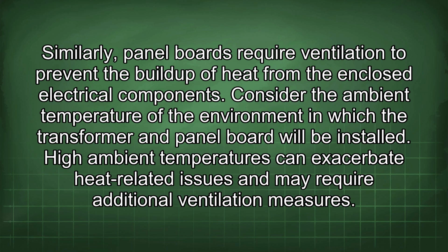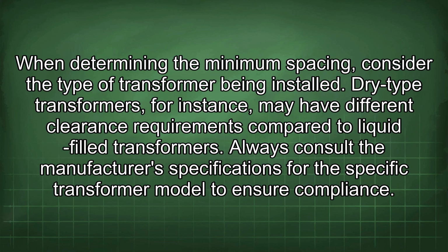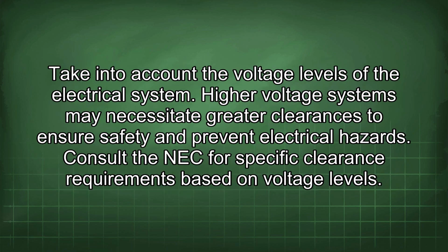Similarly, panel boards require ventilation to prevent the buildup of heat from the enclosed electrical components. Consider the ambient temperature of the environment in which the transformer and panel board will be installed. High ambient temperatures can exacerbate heat-related issues and may require additional ventilation measures. When determining the minimum spacing, consider the type of transformer being installed. Dry-type transformers, for instance, may have different clearance requirements compared to liquid-filled transformers. Always consult the manufacturer's specifications for the specific transformer model to ensure compliance. Take into account the voltage levels of the electrical system. Higher voltage systems may necessitate greater clearances to ensure safety and prevent electrical hazards. Consult the NEC for specific clearance requirements based on voltage levels.